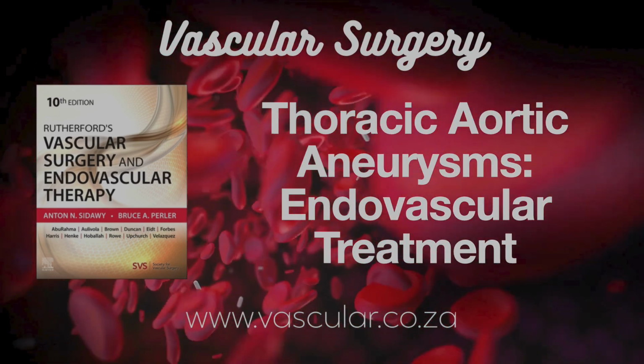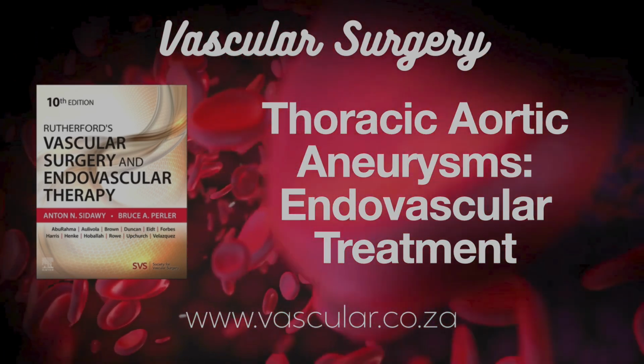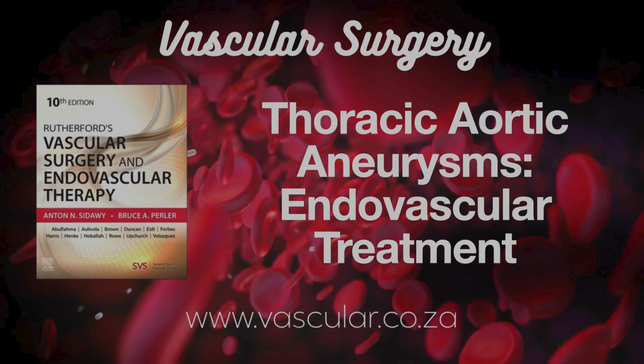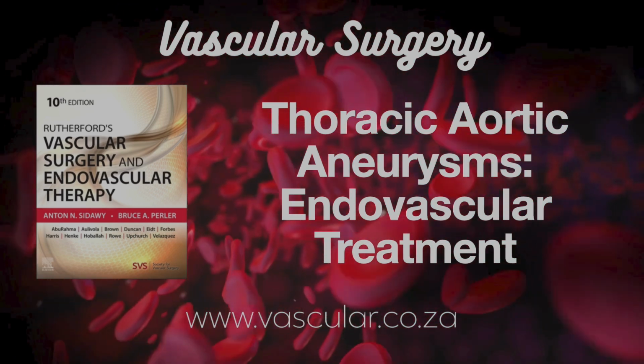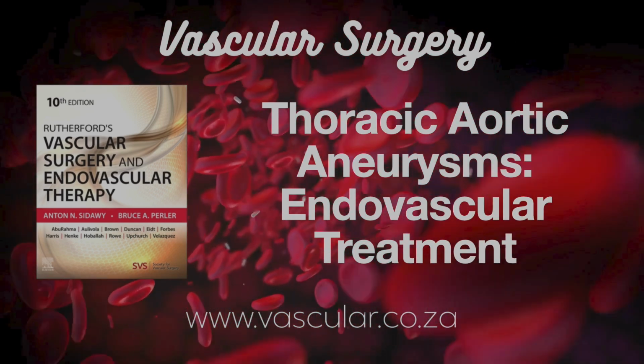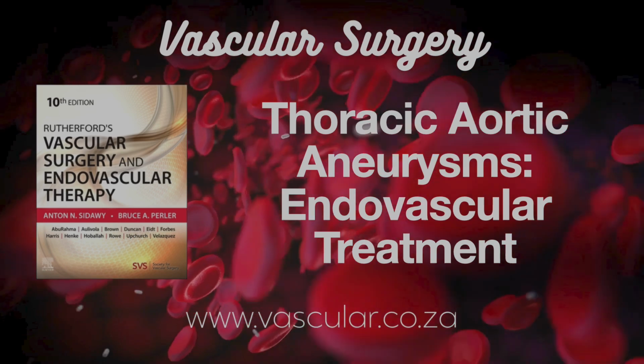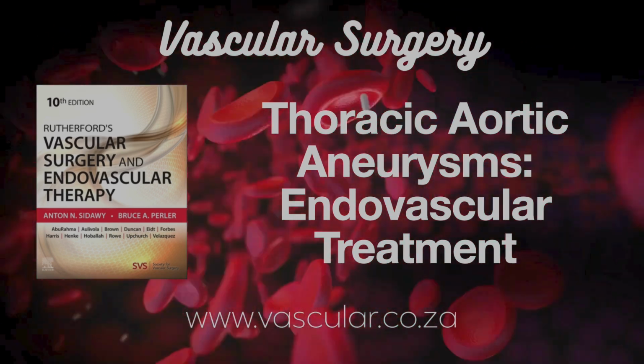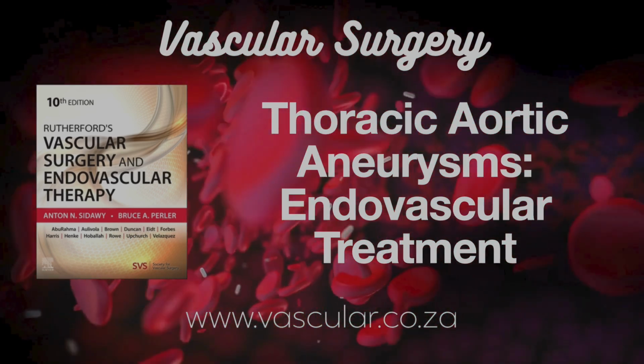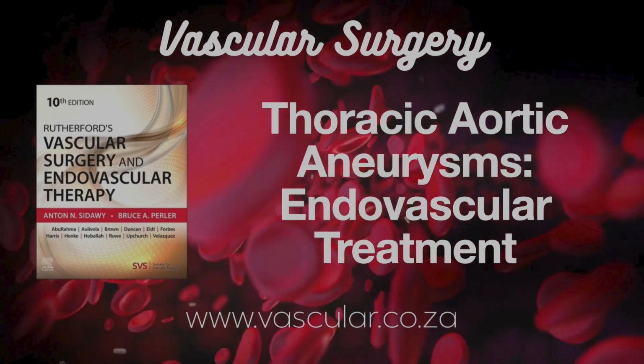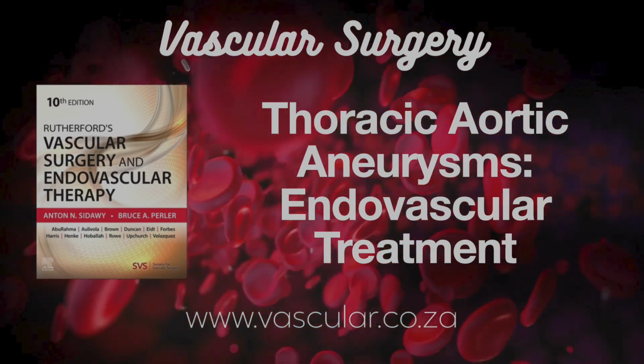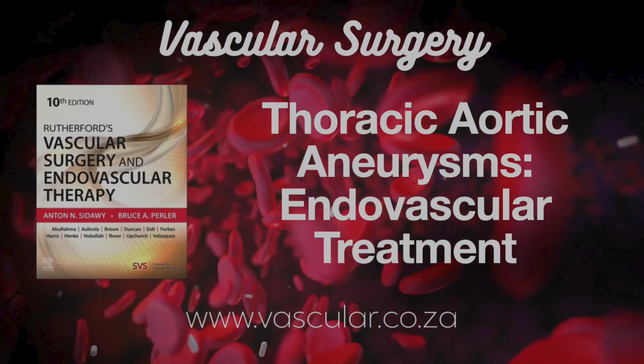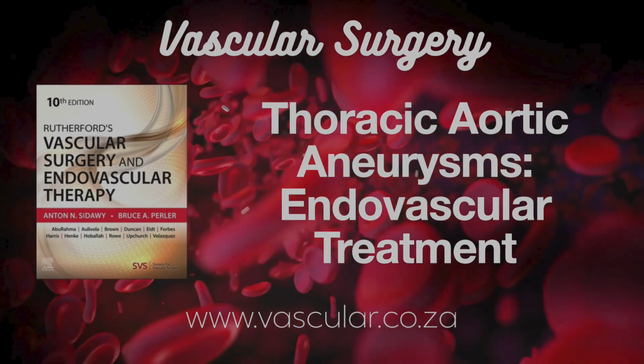Starting with the Gore TAG Conformable with Active Control. That was the first one approved, wasn't it? The original TAG. That's right. Original TAG in 2005. The conformable version came in 2012. And this latest one, the Active Control system, in 2019. What are its key features? It uses an ePTFE graft material, reinforced. Sutureless attachment, nitinol stent skeleton. The big thing with Active Control is this 2-step deployment.